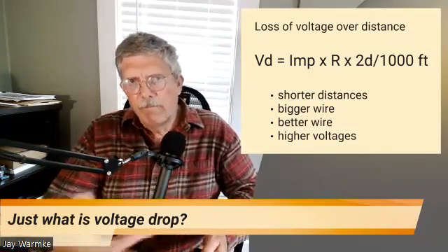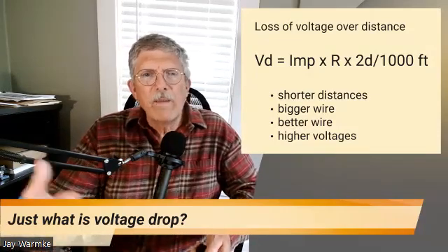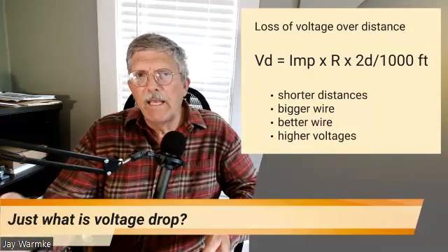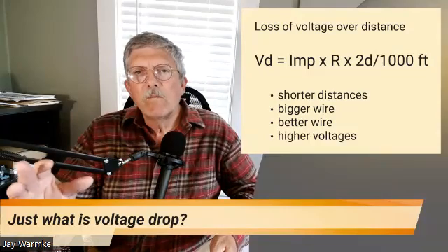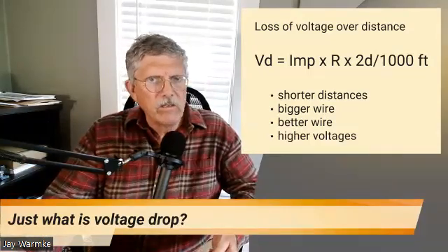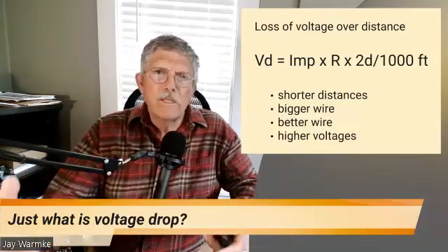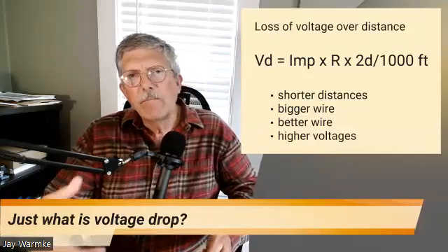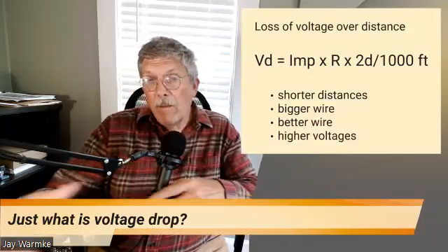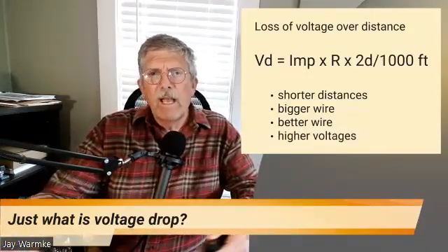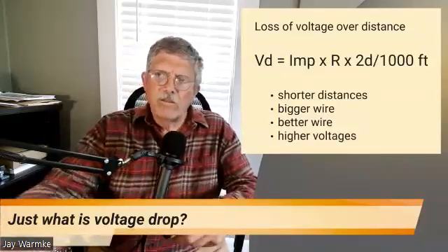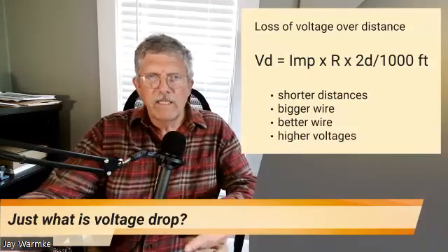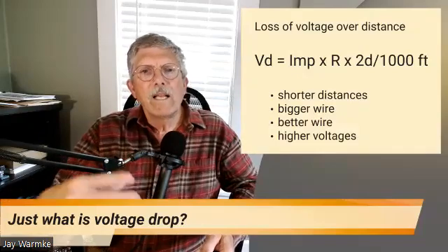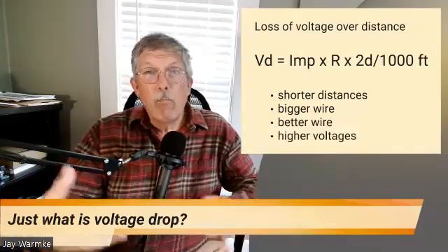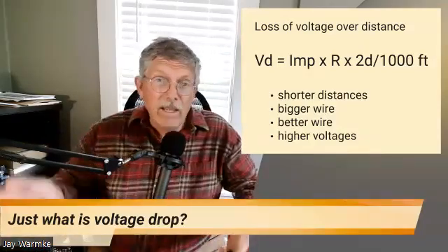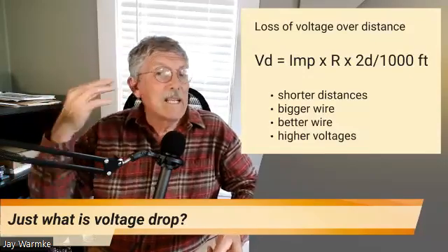So the voltage drop equation for solar is voltage drop equals amps, in this case the IMP, the operating amperage of your solar array, times resistance. You get resistance out of the National Electrical Code, usually given in ohms per 1,000 feet. Then you multiply by twice the distance divided by 1,000 feet, so you're saying how much of 1,000 feet we're dealing with. We say twice the distance because the wire is a circuit: it goes there and it goes back, so the electricity travels twice the distance. If you've got a 150-foot run, the electricity is actually traveling 300 feet. That would be 0.3 of 1,000, and you multiply that times the resistance. There are other ways of finding the voltage drop, but that's the concept behind it.